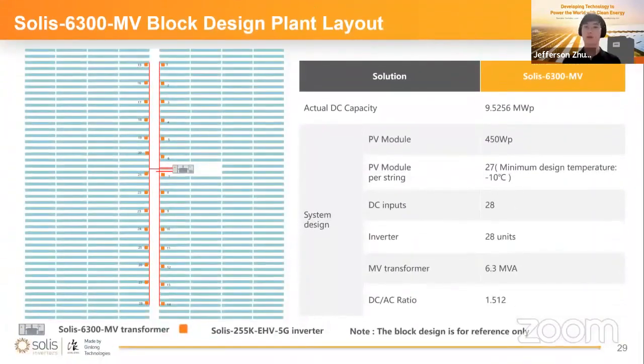Here is a solution estimate. The actual DC capacity for this product can be 9.5256 megawatts. The PV module we designed is 450 watts, and there are 27 PV modules per string. We use a temperature as low as 10 degrees below zero. The DC inputs and inverters are 28 units. The MV transformer is 6.3 megawatts, and the DC to AC ratio is 1.512. This is just a reference. In the future, if you are interested, contact our sales and we can do something for you.